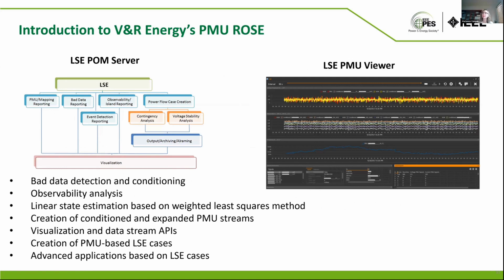The hazard algorithm was integrated with V&R Energy's PMU ROSE, which includes multiple capabilities: linear state estimator, which includes bad data detection and conditioning if possible, observability analysis—more important in LSE than conventional SE since we have fewer PMU measurements than SCADA points—weighted least squares method, conditioning, expanding PMU output streams, APIs, visualization, and creation of PMU-based cases, similar to how we create SCADA-based SE cases, for use in further advanced applications.